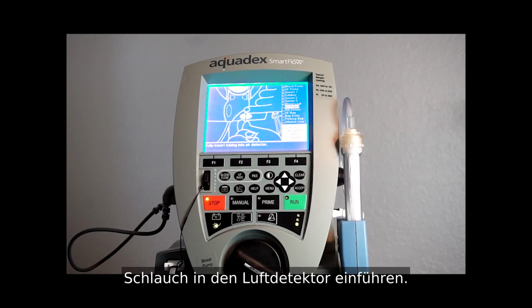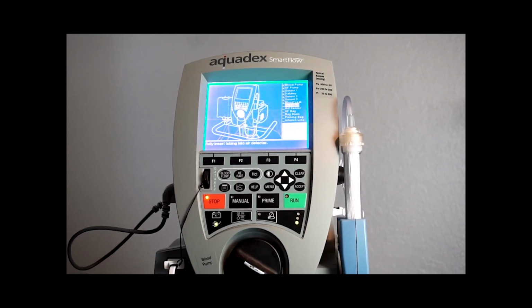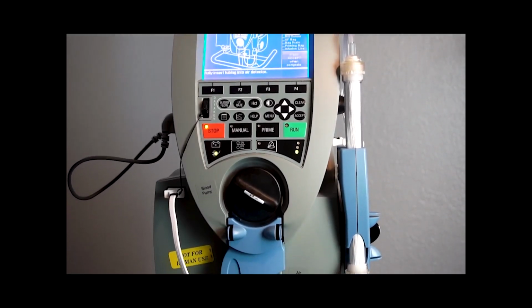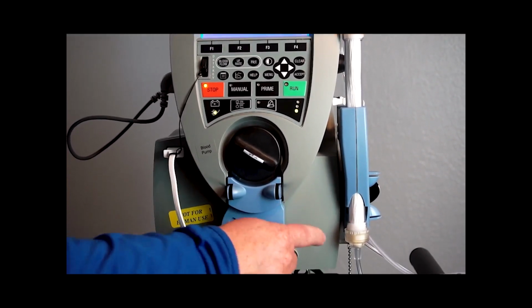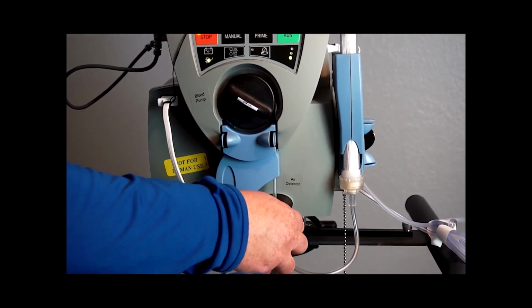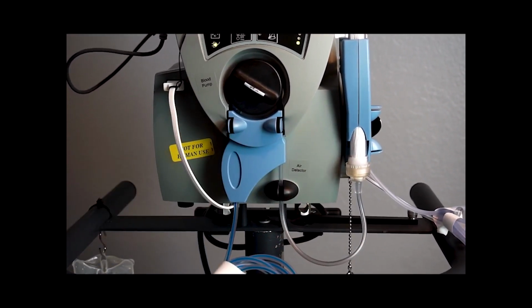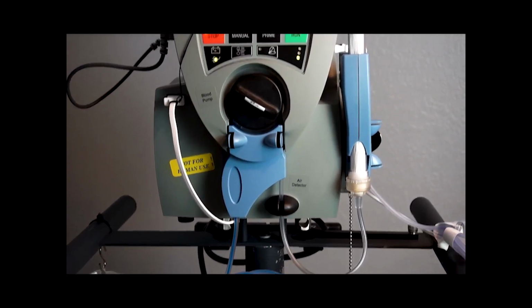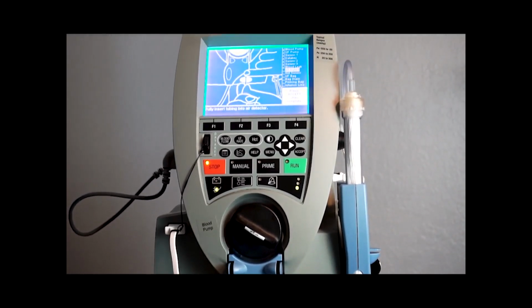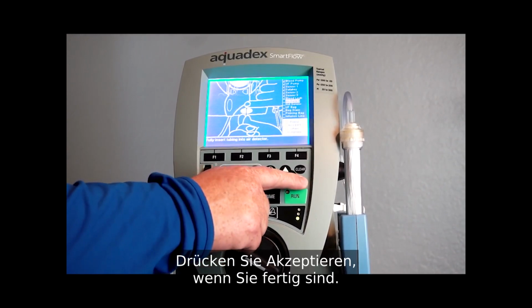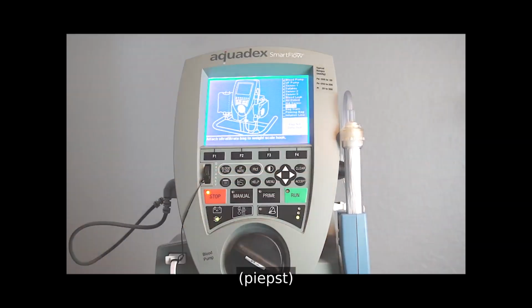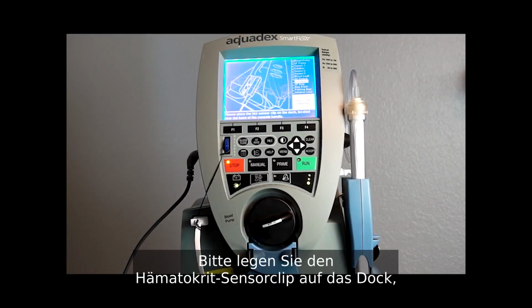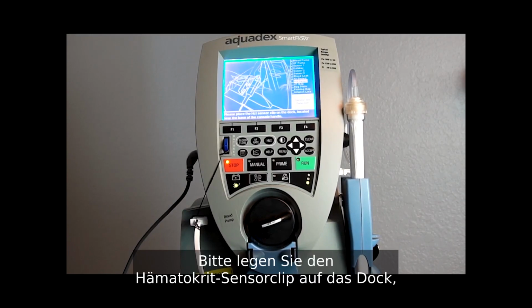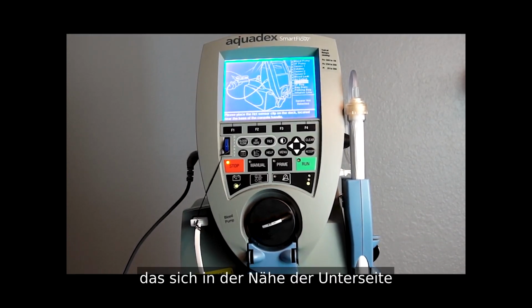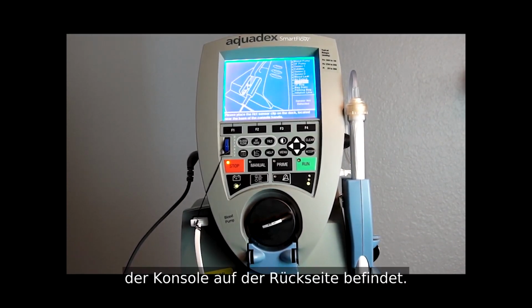Insert tubing into the air detector. Press Accept when complete. Please place the hematocrit sensor clip on the dock located near the base of the console at the rear.